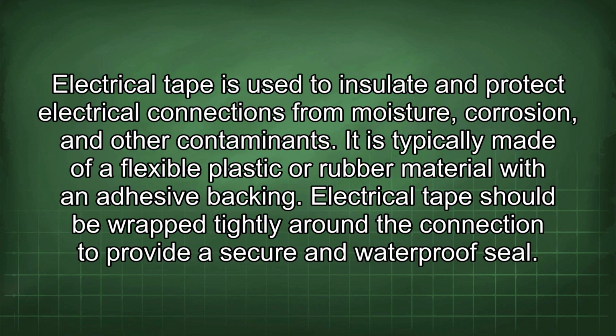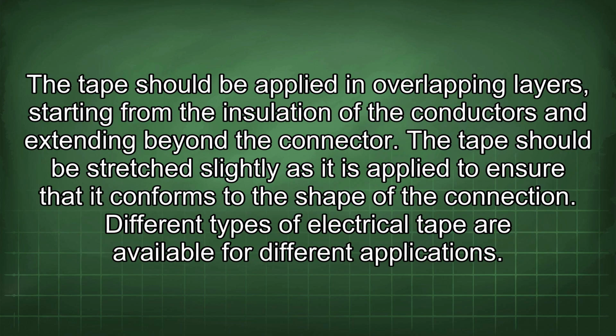Electrical tape is used to insulate and protect electrical connections from moisture, corrosion, and other contaminants. It is typically made of a flexible plastic or rubber material with an adhesive backing. The electrical tape should be wrapped tightly around the connection to provide a secure and waterproof seal. The tape should be applied in overlapping layers starting from the insulation of the conductors and extending beyond the connector.